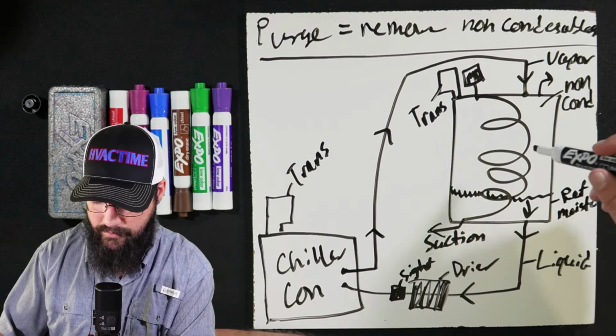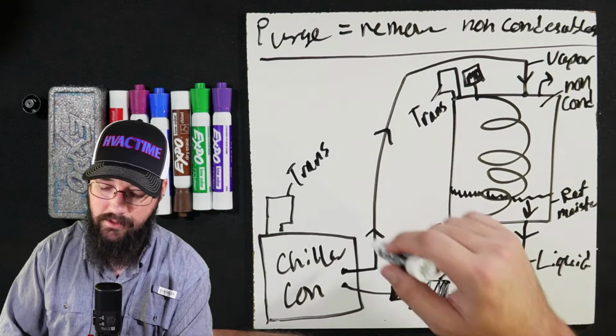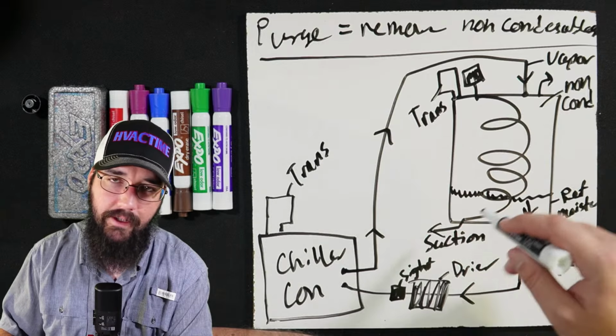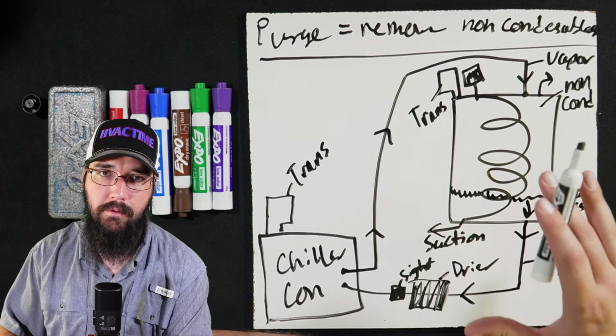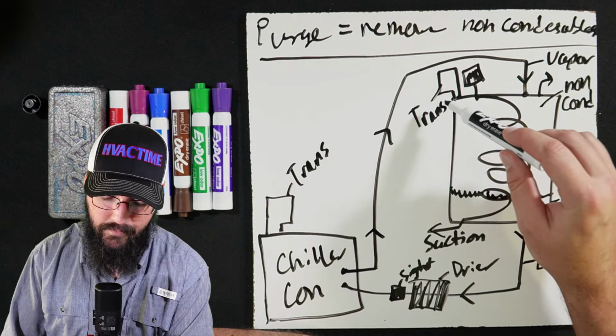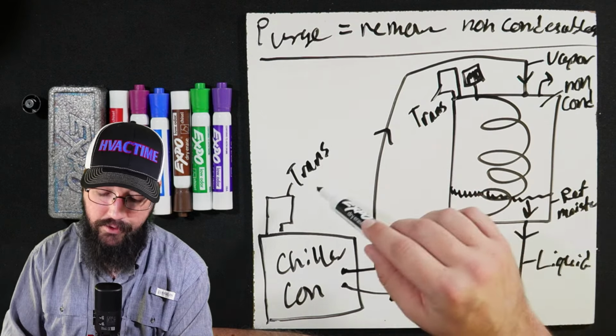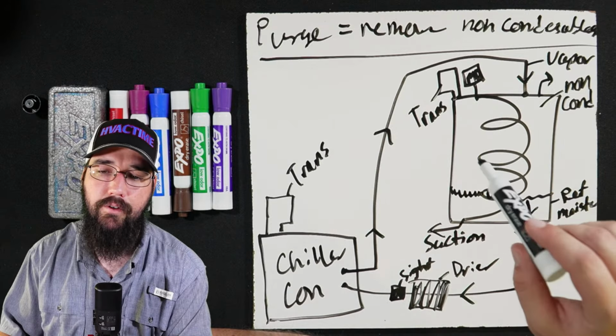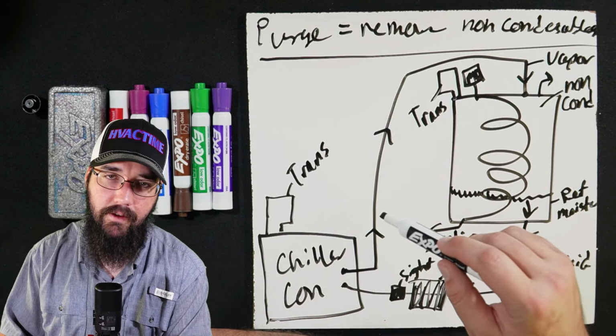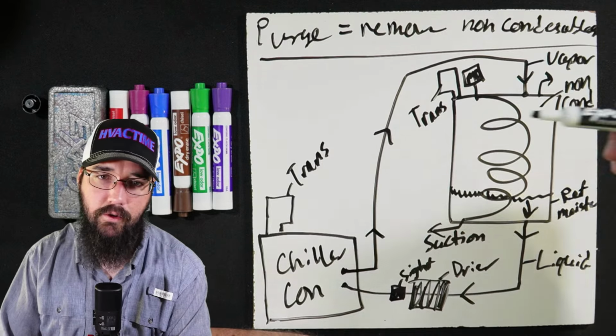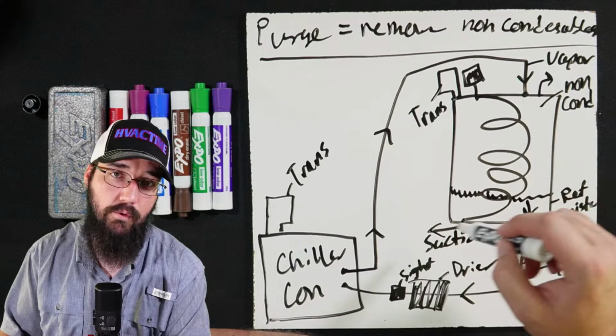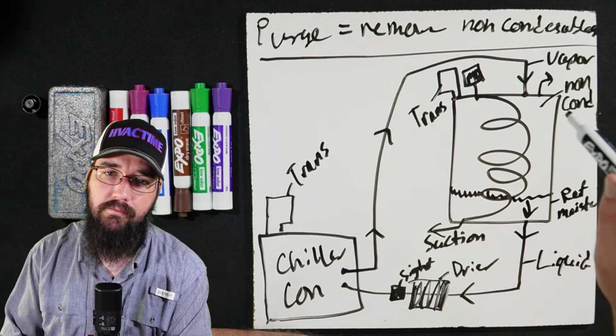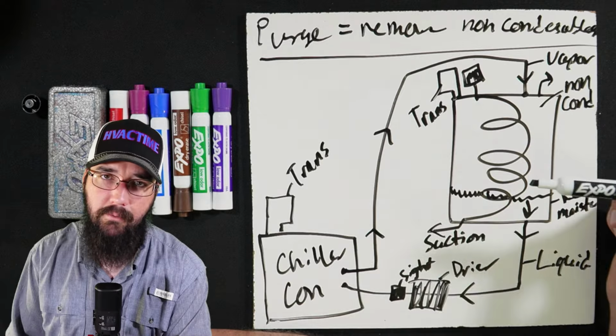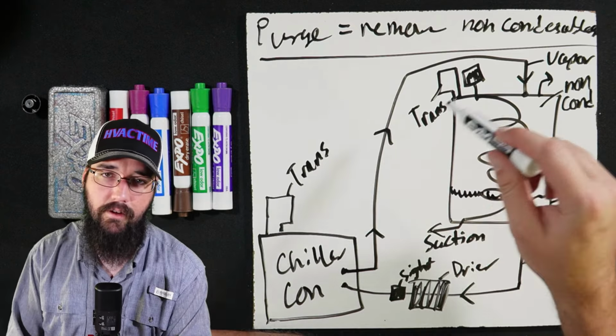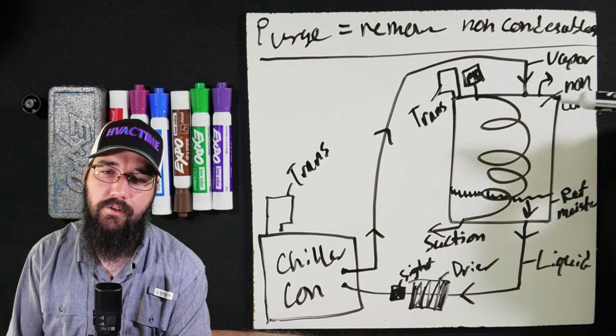So the purge will continue to condense that liquid, and this whole cycle is constantly happening. And this is true for any modern purge unit on the market right now. They're just monitoring the transducer differential in order to determine, do we start to do a pump out or not. So we cross over the threshold, pump out begins, everything else stays doing its thing. We finish pump out, the solenoid closes, the pump turns off, and then it just keeps going until it registers that another pump out is needed.